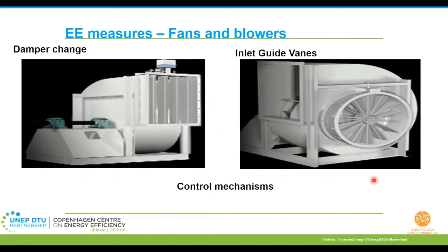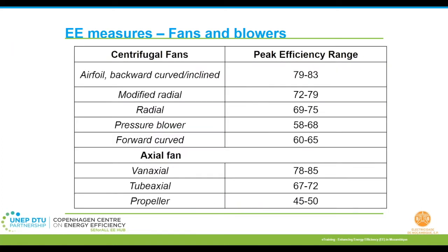So talking about control systems, there is a damper for fans, especially. You have a damper control that can be there at the suction side or the delivery side. Damper is generally the simpler control system, but actually it causes a lot of energy loss. The inlet guide vanes are usually for larger volumes that are handled by the fans. So this reduces your shock losses due to flow deflection, and hence less energy loss is happening here. So here different types of fans and blowers are there, and their approximate peak efficiency ranges for your reference.